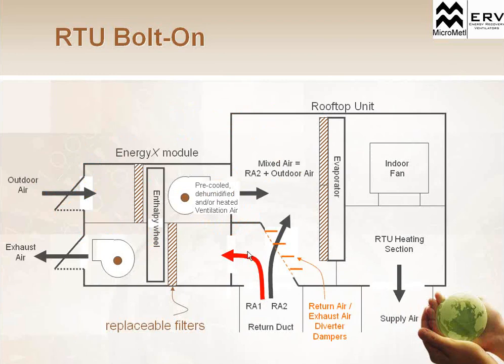With that bolt-on, it's kind of neat. Here's a different layout of the actual bolt-on. So you can see it's not curbed in with the other rooftop equipment. It's actually bolted on the side. Our energy recovery wheel is vertical here. We would have outside air coming in across the wheel into the rooftop unit.